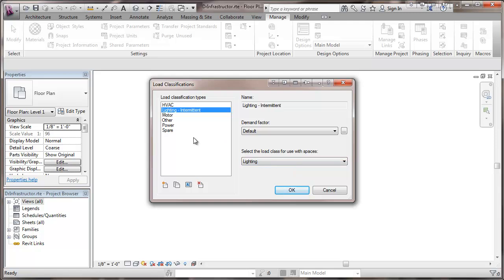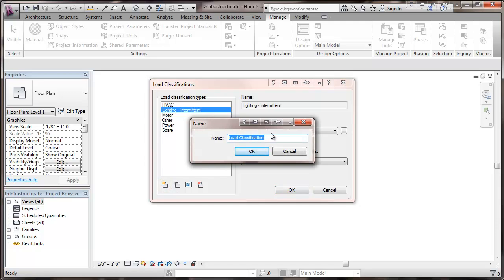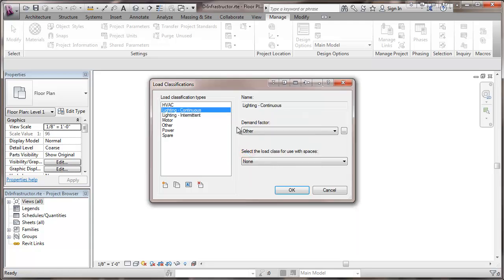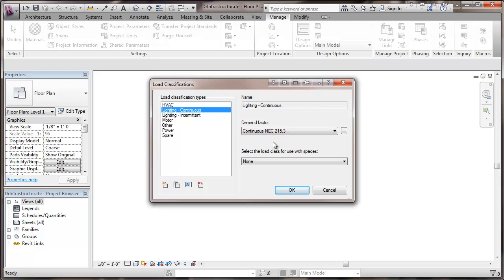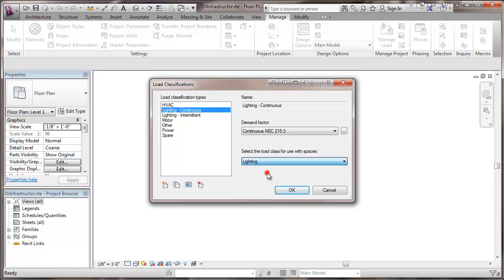And then we're going to add another type of lighting and this will be lighting continuous. This would be lighting as a store or an office where the lighting is left on all day. And for that continuous lighting we're going to go to a demand factor of continuous which is essentially 125 percent which the NEC calls for on continuous loads. Again I'll put this under the category of lighting.